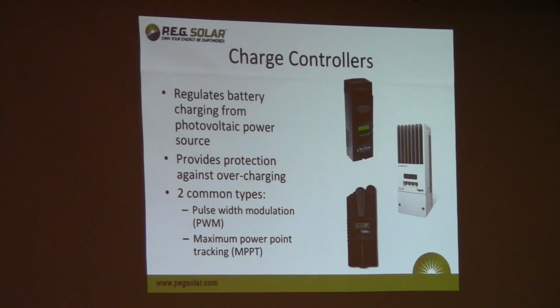So it'll handle self-discharge? Yeah. When this isn't in use, does it have like a tender that keeps the battery at a certain point? Yeah, that's one of the functions the charge controller performs - it gives the battery a daily maintenance charge, keeping it within healthy operating voltage based on the battery chemistry. Then, depending on what type of inverter system you have, it may invert the extra power and sell it back to the power company, or just invert only what's needed to power the loads inside your house. So there are a lot of ways we can do this.